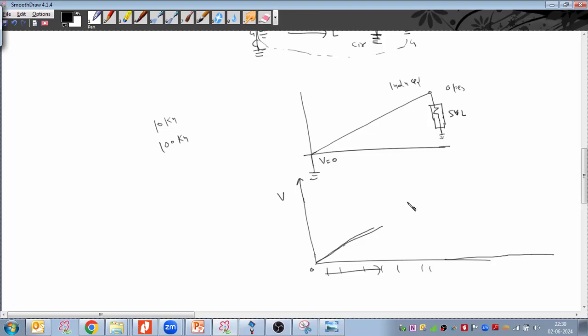Now at this point, when the 65 volts comes after the measurement, we have to break the sheath. After breaking the sheath, we connect the SVL. Again, not grounding, just breaking and putting the SVL, and then taking another section. They are called minor sections and major sections, so the whole length of the cable is divided into multiple minor and major sections.